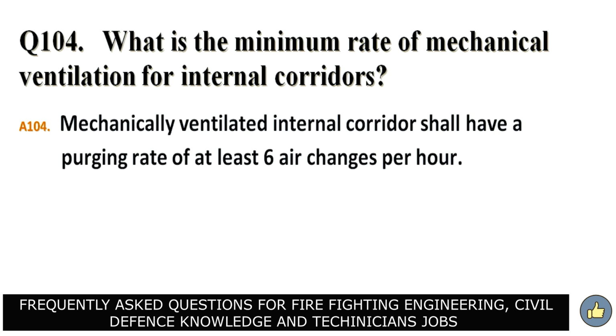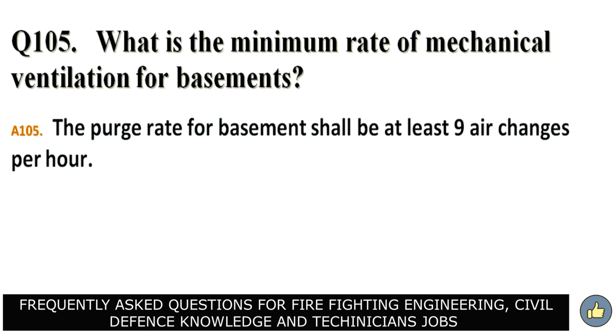What is the minimum rate of mechanical ventilation for internal corridors? Answer. Mechanically ventilated internal corridors shall have a purging rate of at least 6 air changes per hour. What is the minimum rate of mechanical ventilation for basements? Answer. The purge rate for basements shall be at least 9 air changes per hour.